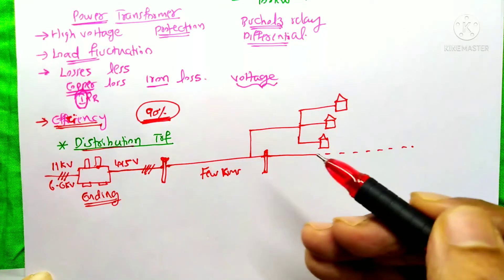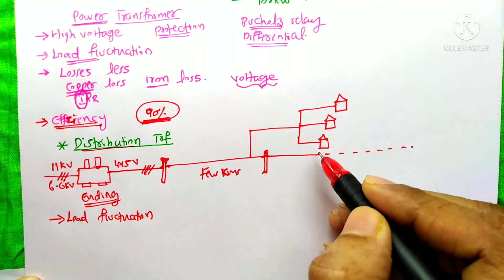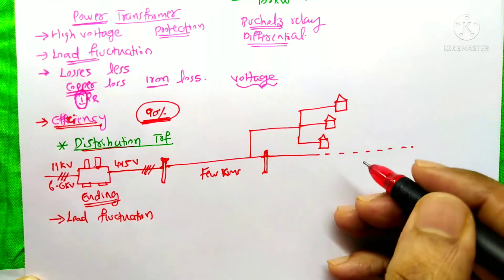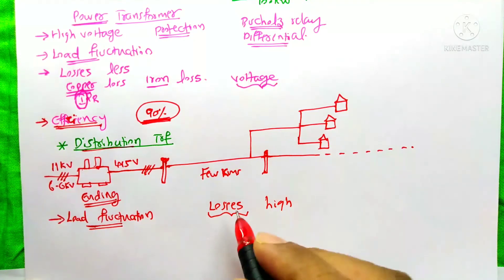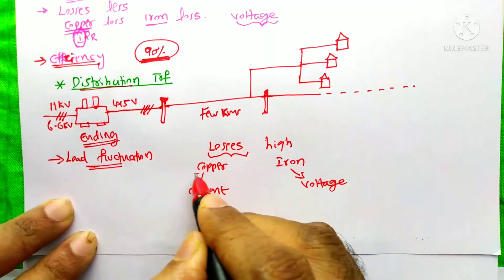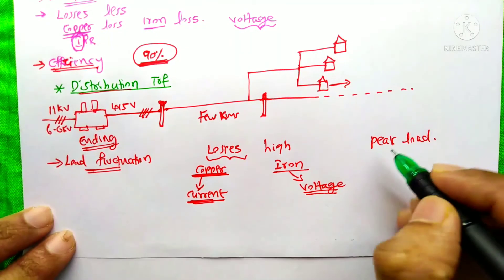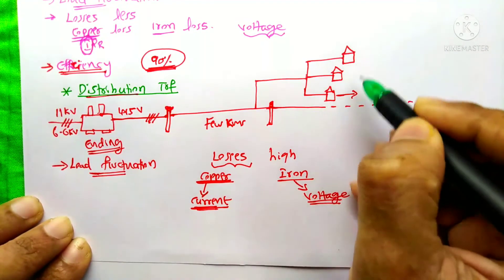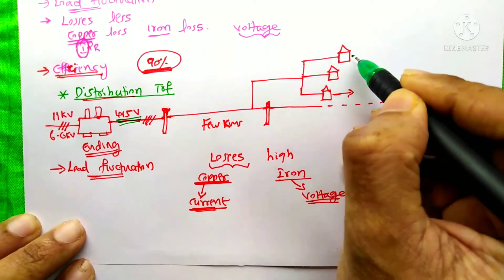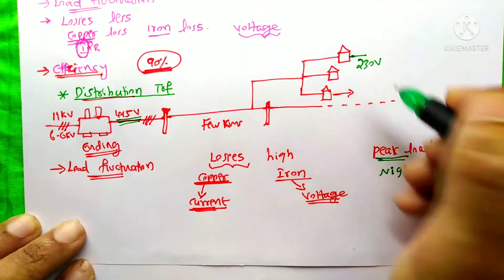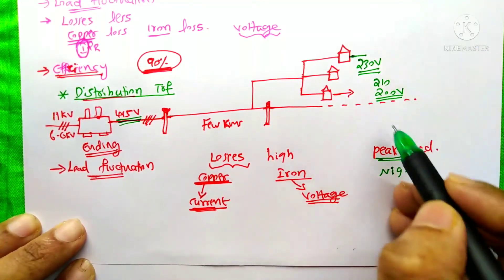After this distribution transformer there would not be any other transformer. Load fluctuation is very high for the distribution transformer — we don't know when each consumer will switch their loads on or off; at any time, anything can happen. Because of this high load fluctuation, the losses in the distribution transformer are high. Iron losses increase at peak load time, which mainly happens at night when all loads are on simultaneously. At that time the distribution transformer cannot deliver the full 415 V; for single-phase consumers at 230 V, you might measure only 210 V or 200 V — that is the voltage fluctuation.